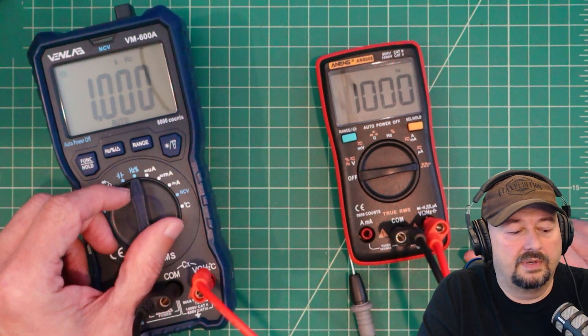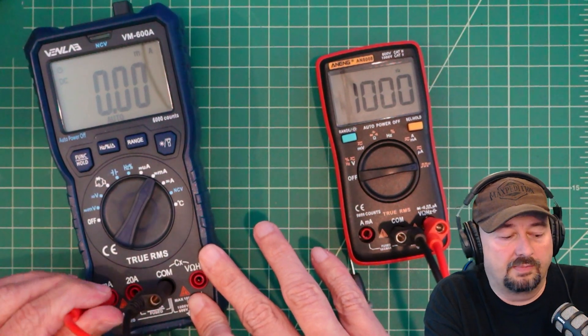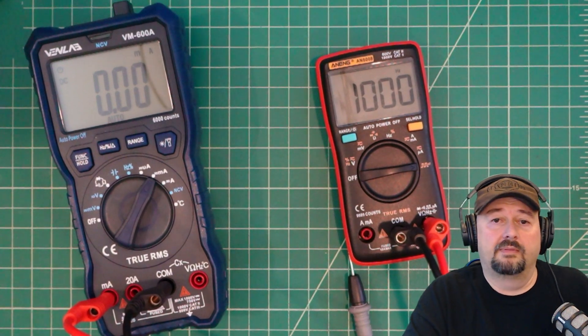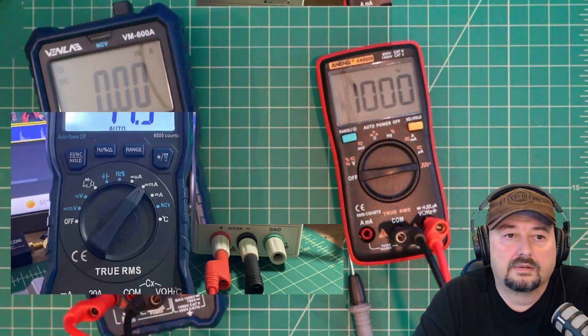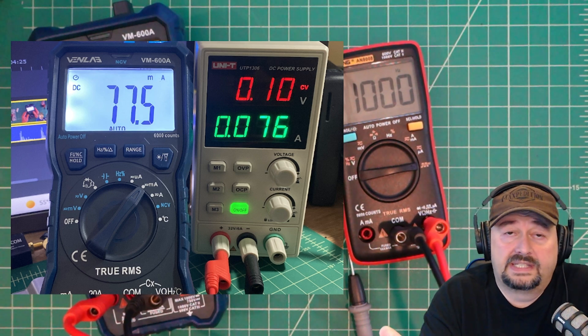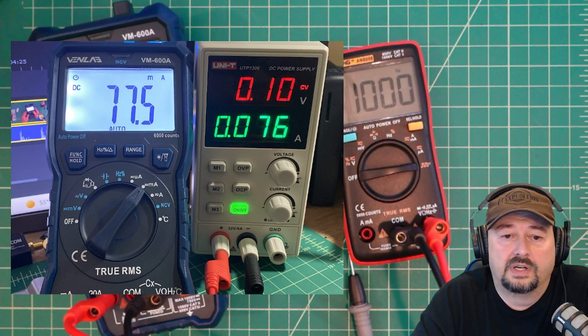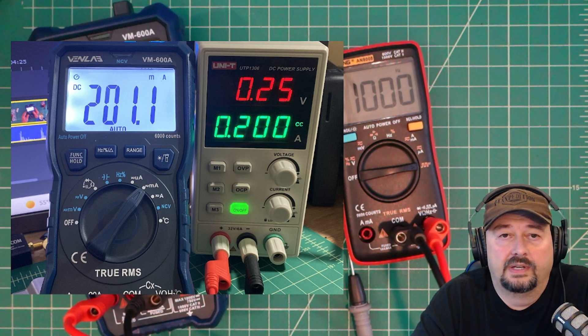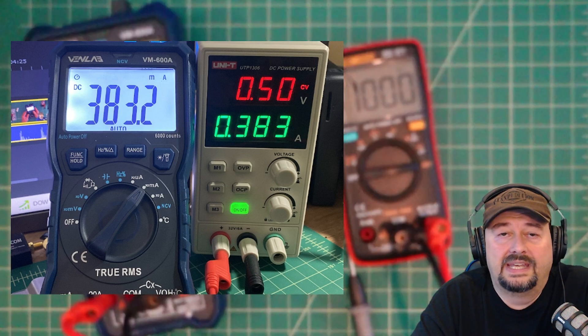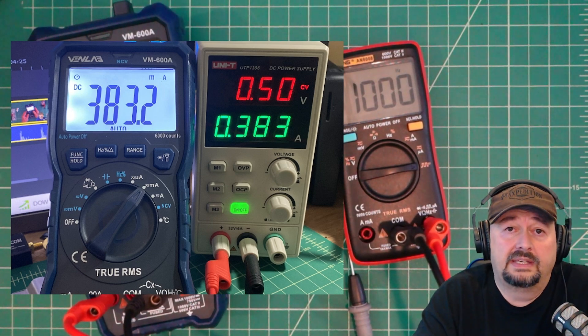We're going to test milliamps. For milliamp testing you disconnect from the voltage port and move to the milliamp port. Rolling in images from my UNI-T power supply: at 0.076 amps (76 milliamps) the meter reads 77.5. At 200 milliamps it reads 201 — within spec. At 383 milliamps the Venlab matches as well. It's measuring accurately at very low current levels, which is great.